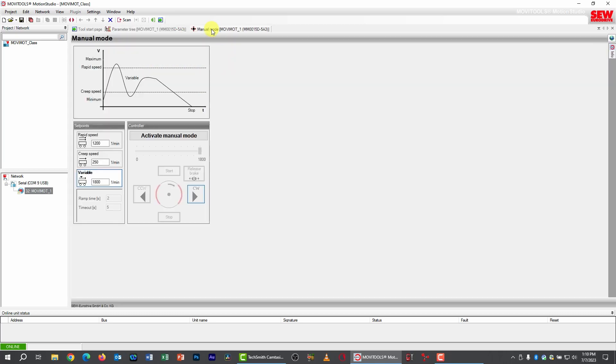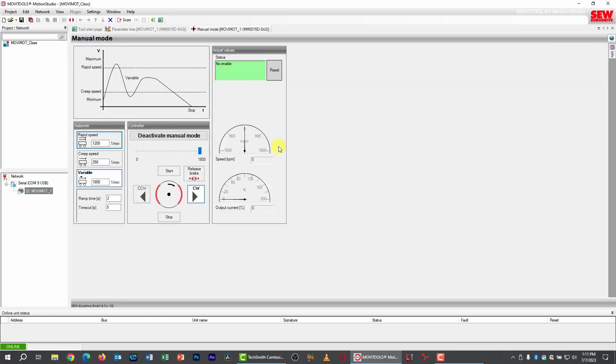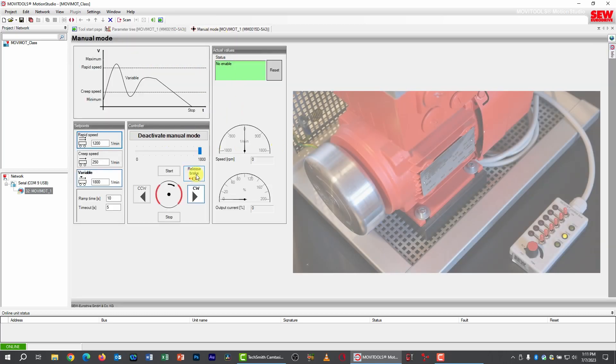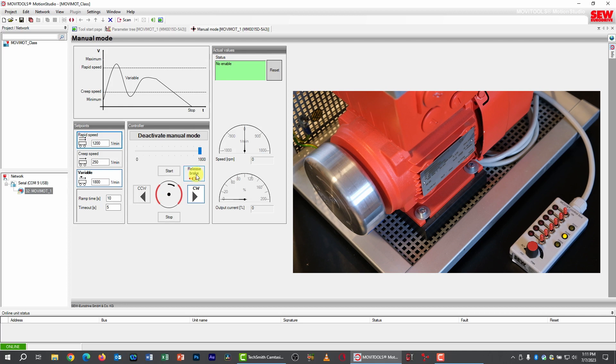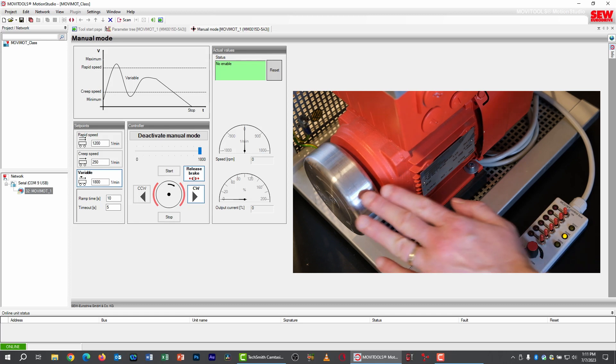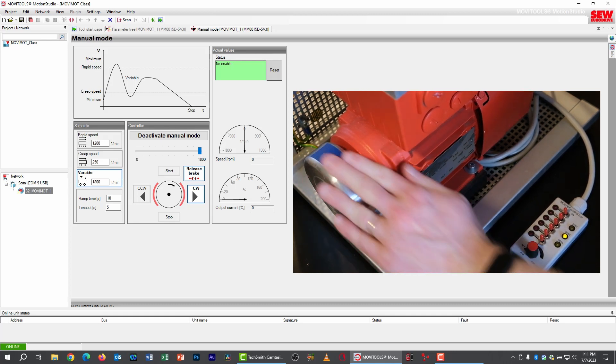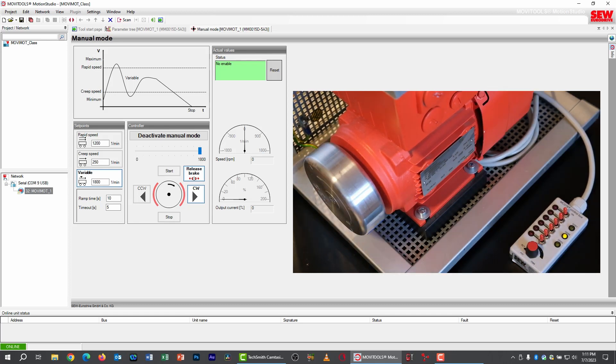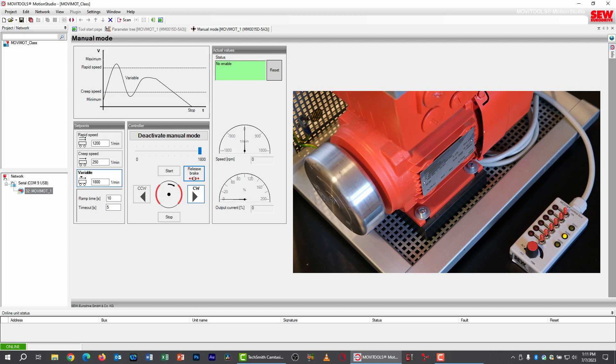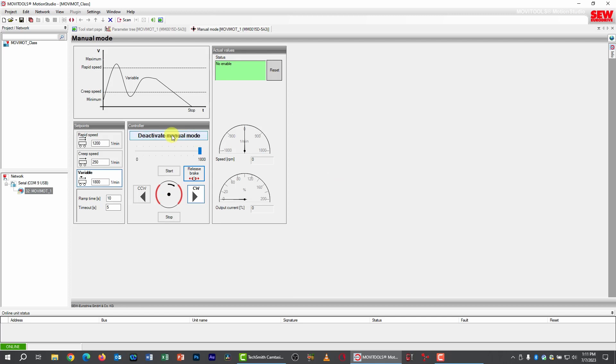And so this mode enables you to do that. And you can do it through manual mode as soon as you turn this parameter from off to on. Let's go back to manual mode and reactivate it. You notice the release brake button is now available. So I'm going to click this and watch the brake symbol around the little motor. You notice it shows the brake released. Now the motor isn't turning. We haven't actually started the motor. But notice that I can turn the motor by hand because the brake is released. So that is something that you can do if you enable that feature either by the DIP switch or by turning that parameter on. Let me close the brake up again. There we go. And now, of course, we couldn't turn it by hand because the brake is holding the motor fixed.